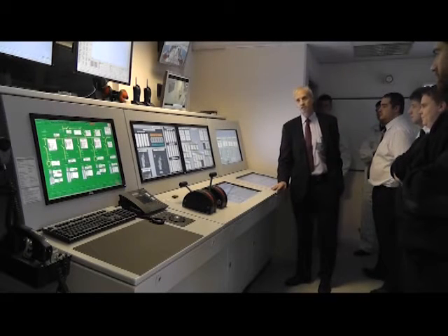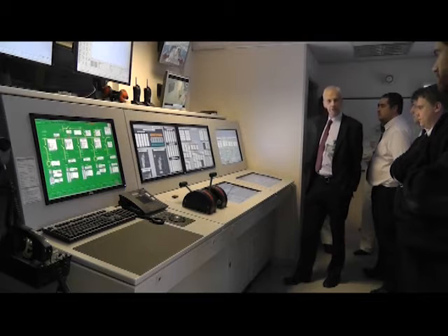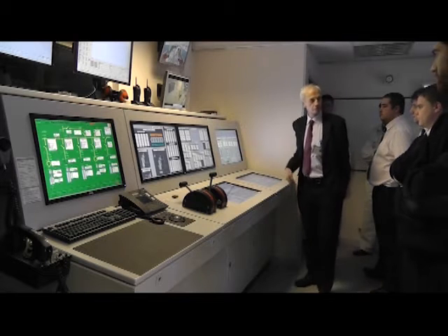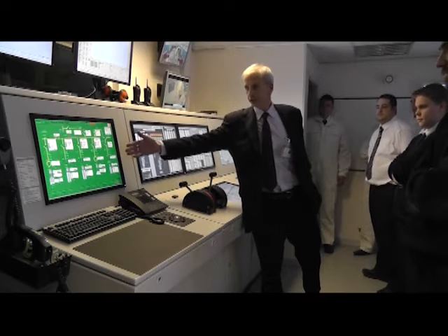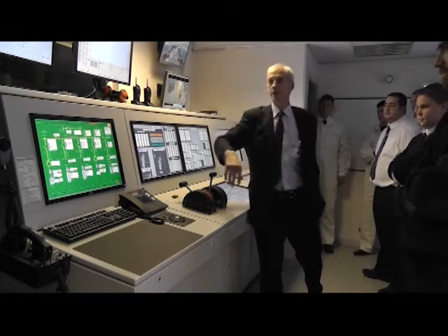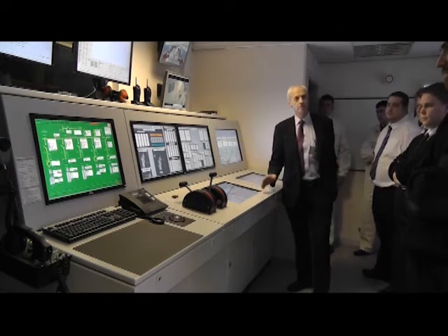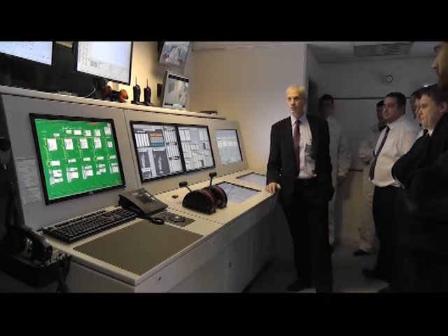Within 45 seconds the emergency generator will start, and you can hear it kicking in now, running up to speed. If we look at the mains power diagram you'll see that once it's running it's connected and it's supplying emergency power. That emergency power will now allow the control system to resurrect the plant.